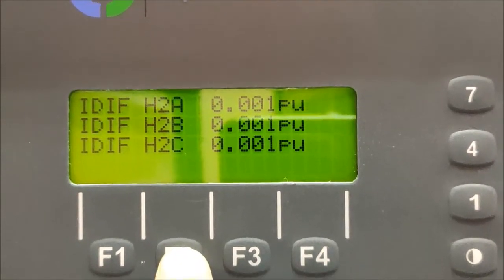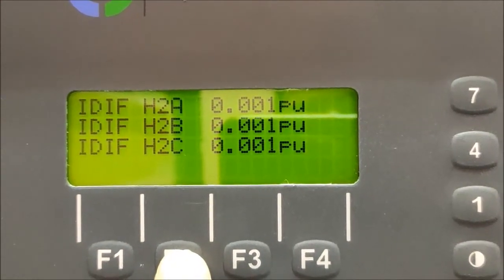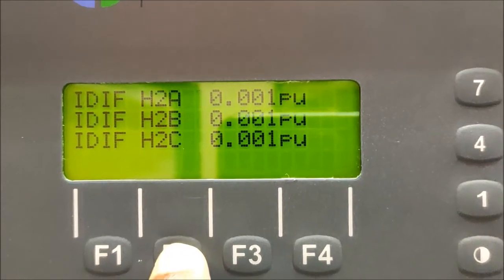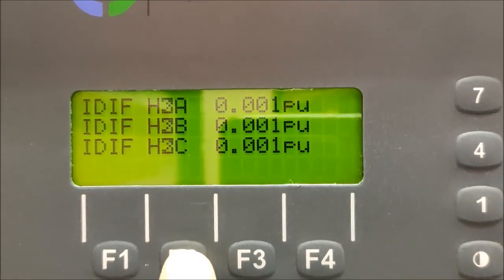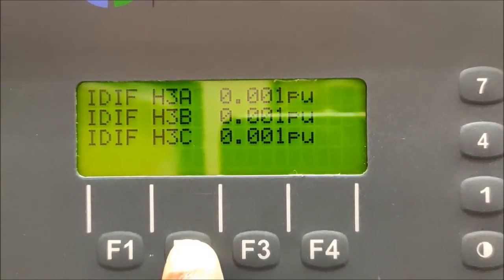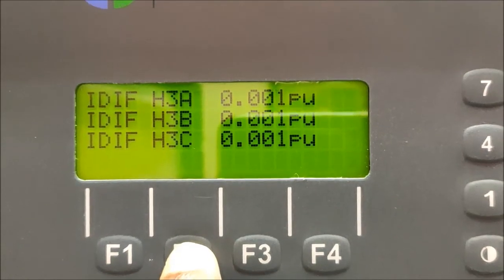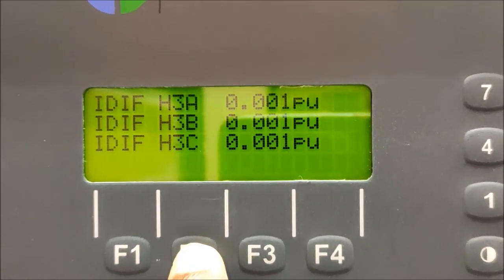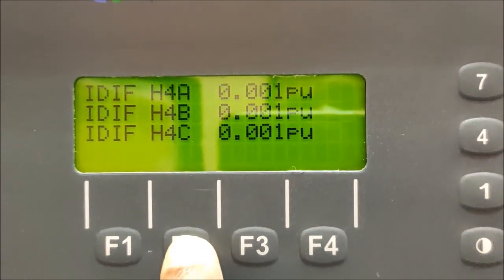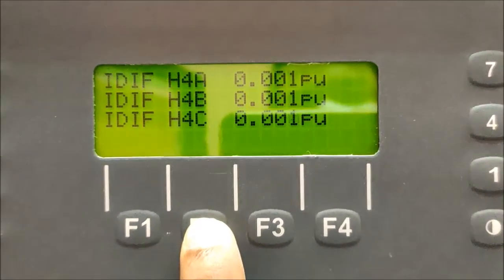Then press F2 again, and you will get the value of second harmonic content — that is I-differential for all phases, which is 0 per unit. Then press F2 again, you will get the third harmonic content value. Then press F2 again, you will get the fourth harmonic content value.